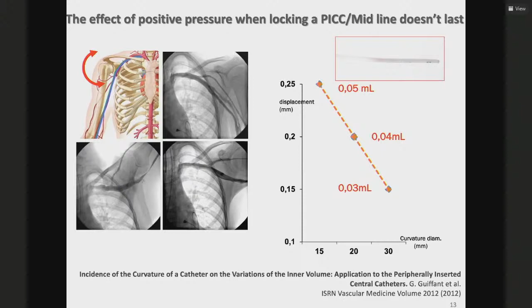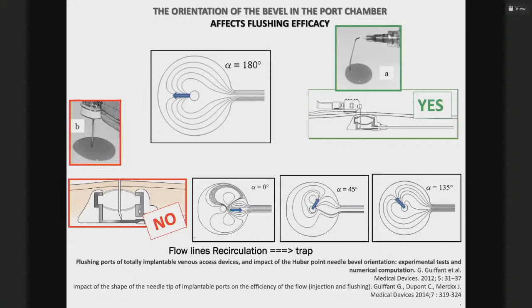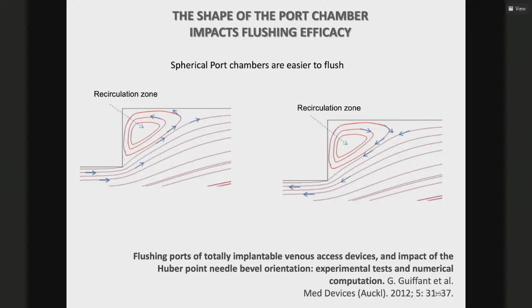We all know that non-coring needles are required for puncturing a septum membrane in order not to damage it. But the importance of the bevel and the way it is oriented inside the port chamber are underestimated. The bevel should be oriented like this, in the opposite direction of the catheter connection with the port, in order to increase flushing efficiency. Keep in mind that it's very difficult to clean a port because of its corners.